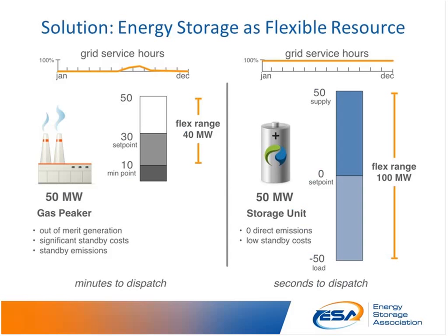These systems are very flexible. When you're looking at a gas peaker to try and do some of this, it segues back towards peaking plants, but these facilities are also used for frequency response. These gas peakers need to sit there online idle, burning fuel, ready to go, because they have to be warmed up - you can't cold start them and just go off to the races. These peaker plants are inefficient and also have about a 40 megawatt flexible range.